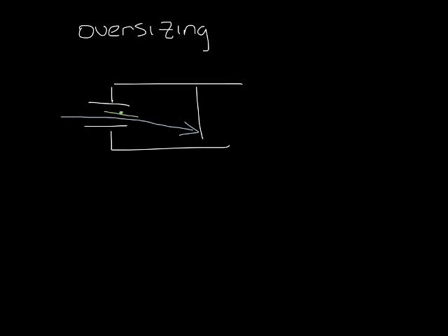This can actually have the reverse effect. By increasing the size of the VAV box, the damper will be closed more to maintain airflow. So let's say we have this box sized correctly. As the airflow comes in, because the damper is wide open or close to wide open at design, the air comes straight through the box.